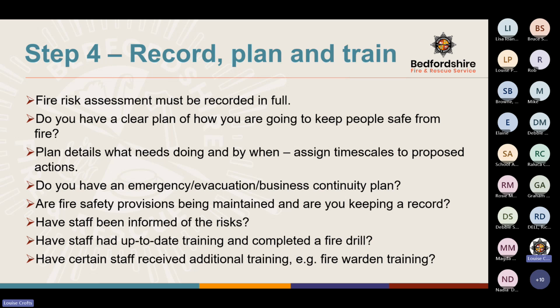So any fire safety provisions that you have, so your fire alarm system, your emergency lighting, your fire extinguishers, are they being maintained? Depending on what you have, for example, if you have a commercial fire alarm system, the requirement under legislation is that you'll have that serviced by a competent person every 6 months. Emergency lighting will be serviced annually, as will fire extinguishers. But then with your emergency lighting, you need to be doing your testing, your monthly flick test. Your fire alarm, you'll be doing your weekly test. So it's making sure that things are tested and maintained, and that you're keeping a record of that.